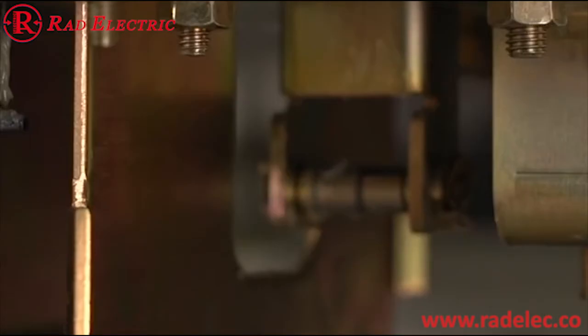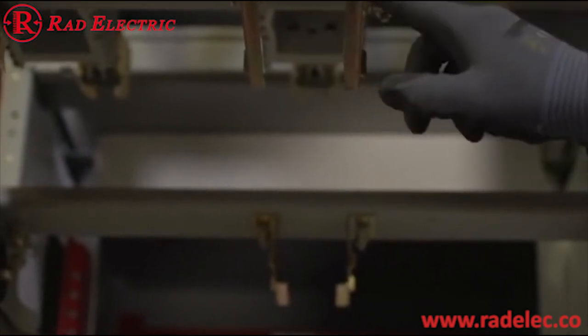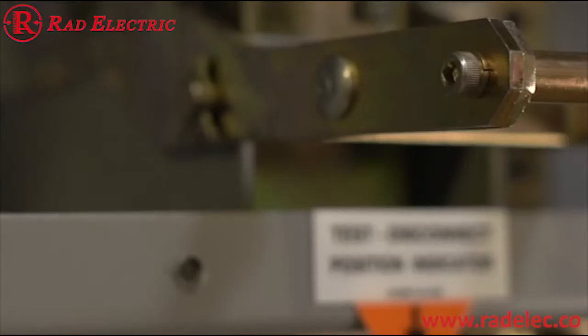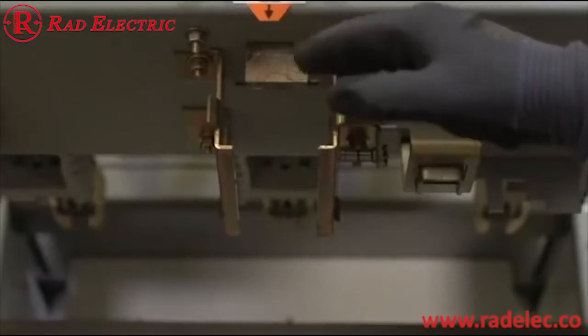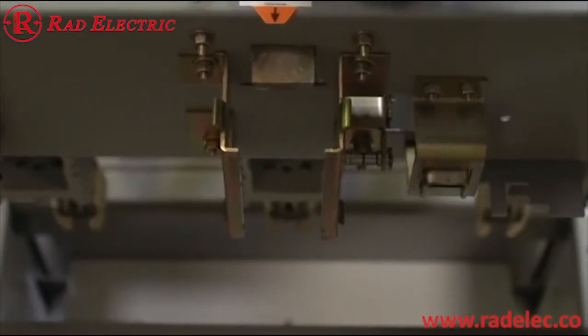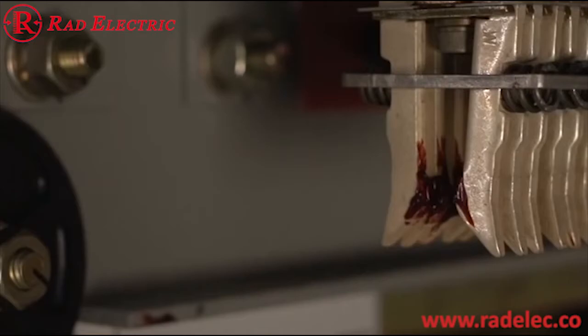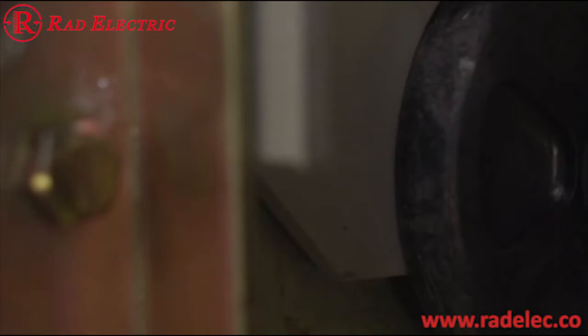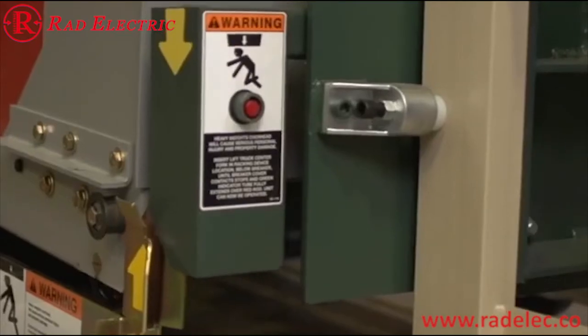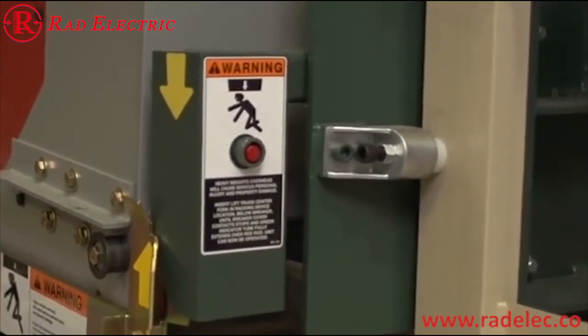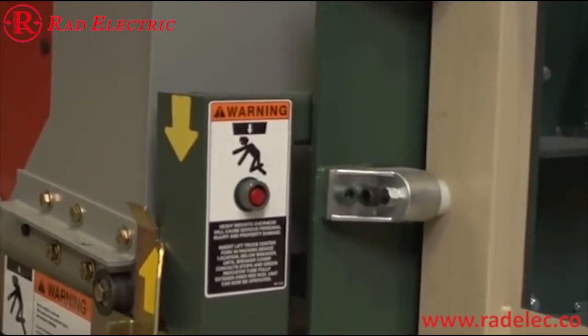This is the guide rail. It helps align the circuit breaker in the compartment. Here we have the circuit breaker interference plate to help ensure an adequately rated circuit breaker is being inserted into the cell. The latch mechanism attaches to the drive block, which moves the circuit breaker as you rack it. To remove the circuit breaker, push down the latch release. The circuit breaker moves on the floor on these rugged polycarbonate wheels, secured by steel hardware. Note that there's another set of smaller metal wheels that connect with the rails as the circuit breaker is inserted into the cell.